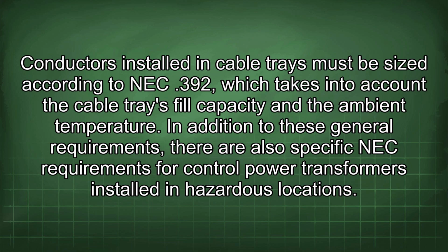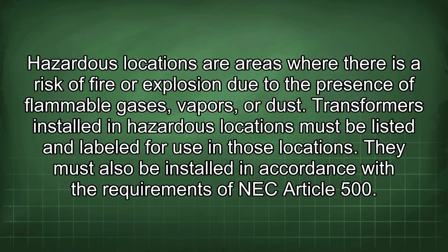In addition to these general requirements, there are also specific NEC requirements for control power transformers installed in hazardous locations. Hazardous locations are areas where there is a risk of fire or explosion due to the presence of flammable gases, vapors, or dust. Transformers installed in hazardous locations must be listed and labeled for use in those locations. They must also be installed in accordance with the requirements of NEC Article 500.